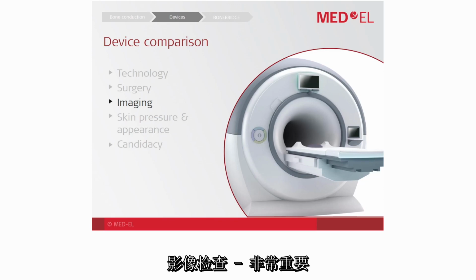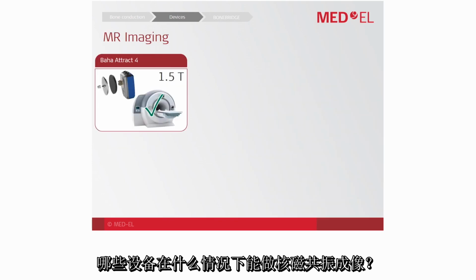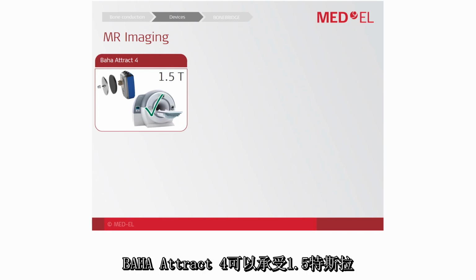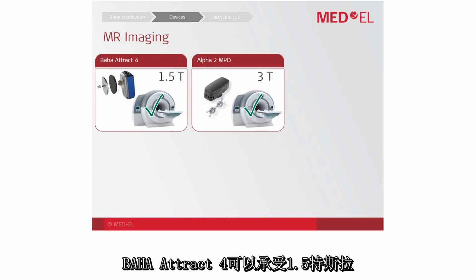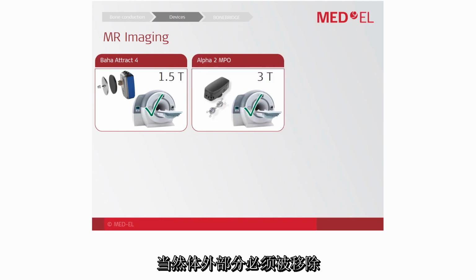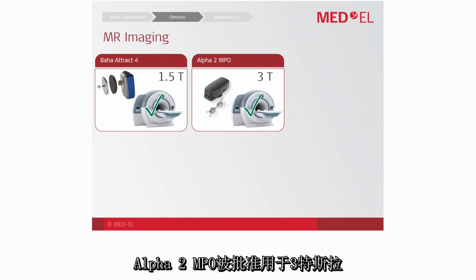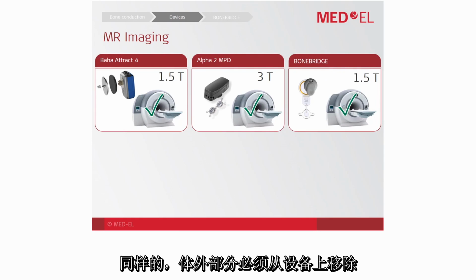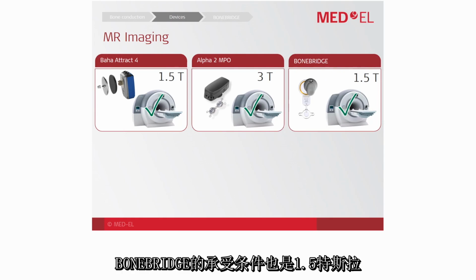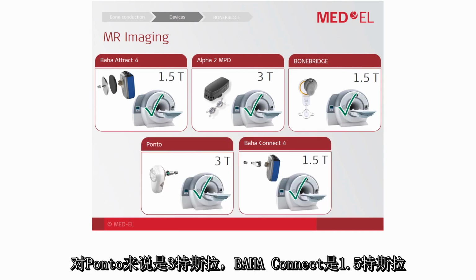Imaging, very important. So, which devices are conditional to MRI imaging? The Baha Attract 4 is conditional at 1.5 Tesla. Of course, the external part has to be removed. The Alpha 2 MPO is approved for 3 Tesla. Also here the same. The external part has to be removed for all devices. The Bonebridge as well is certified conditional for 1.5 Tesla. The Ponto 3 Tesla, and the Baha Connect 1.5 Tesla.